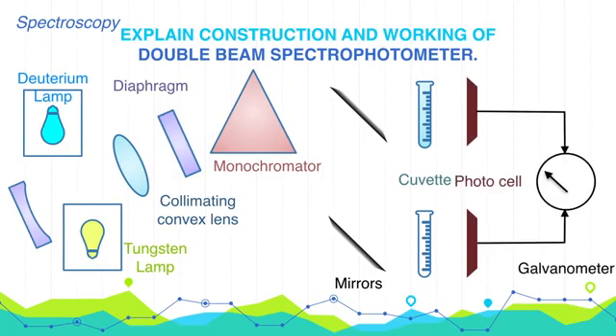Finally, there are two photocells placed. One is connected to the cuvette containing sample solution and the other is connected to the cuvette containing blank or solvent. Finally, these photocells are connected with the computer so that we can get the signal.